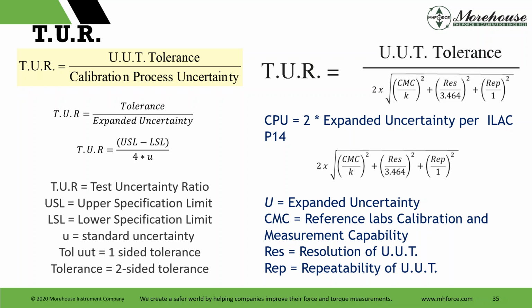And typically, we're looking back, remember that ILAC P14. Remember that, the short-term contributors? This formula comes out of the ANSI Z540.3 handbook. They discuss what should be in the denominator of the TUR. It's also inferred by ILAC P14 in section 5.4. It's inferred with short-term contributors that these would be, at minimum, the resolution of the UUT and the repeatability of the UUT.